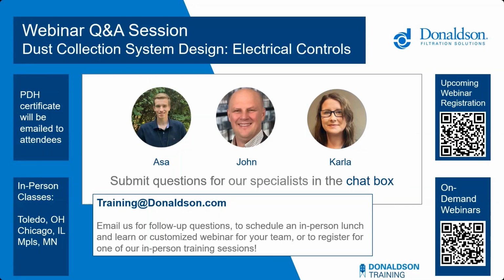Photohelic gauges are very similar to Magnehelic gauges, except they do have, I believe, electronic contacts that you can use to set your set points, both high and low. At Donaldson, we use Magnehelic gauges fairly frequently on some of the simpler collectors that we mentioned earlier. We don't really use Photohelic gauges anymore. We have phased those out in favor of digital differential pressure readings. We handle a lot more of that, including the set points on the digital interface, either on the Delta P or the new Contura controller. So we just don't see Photohelic pressure gauges used nearly as much anymore. You still could. You can get your set points off of them and you can still operate a collector, but they aren't as common.